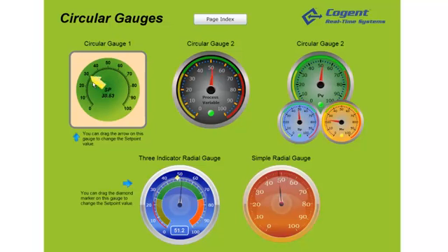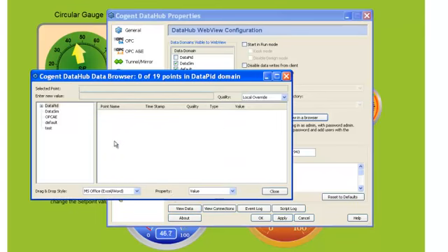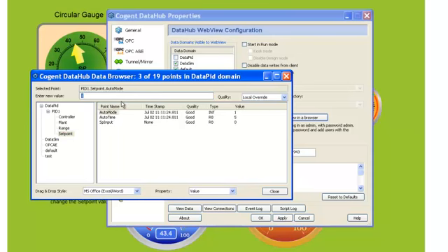But you'll notice that as I move this gauge around the screen, it's actually fighting with me. You can see that I'm trying to drag this all the way over to say 90 or 100, and it's actually not moving. The changes that you're seeing here are because auto mode is set. And in fact, maybe I can just illustrate a little bit more clearly. I'm going to go to the Data Hub properties window, and I'm going to open up the property that controls the auto mode. So here is my auto mode setting, and you'll see it's currently set to 1.